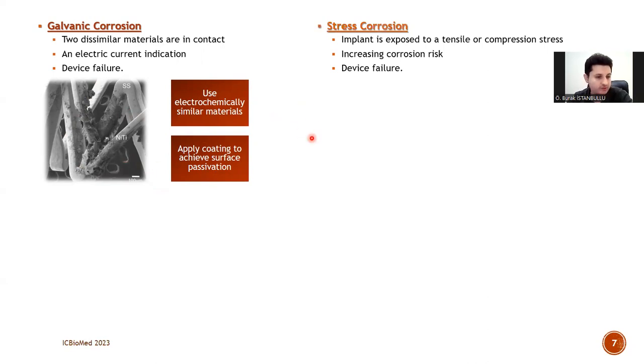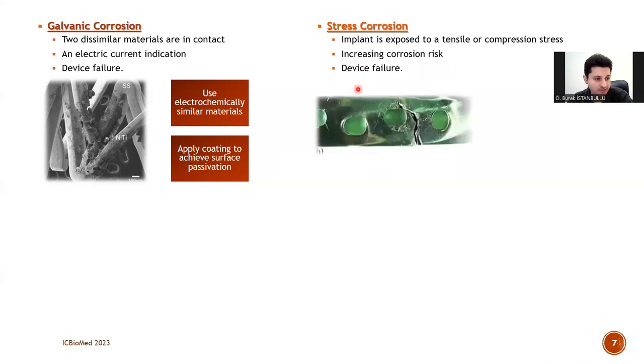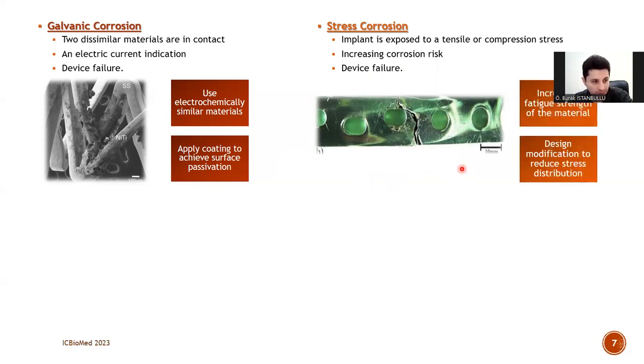Another common corrosion issue for biomaterials is stress corrosion. This occurs when an implant is exposed to tensile or compressive stress, such as body weight. This may increase the corrosion risk and lead to device and material failure, as shown in the cracked bone plate picture given here. Increasing the fatigue strength of the material or making a design modification that reduces stress distribution on the material surface can also reduce or completely block stress corrosion issues.